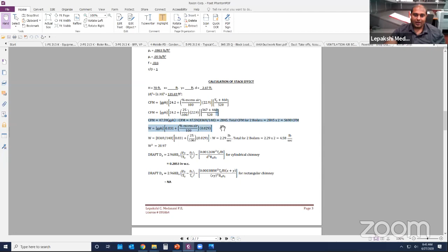So with all this information, I'm having 0.2853 inches water column of draft available with that chimney. With the 70 feet high chimney, I'm already having 0.28 inches of draft, which means this is the positive draft.